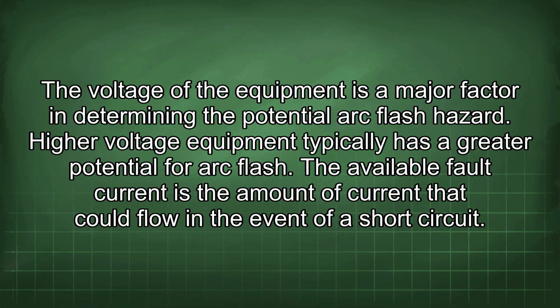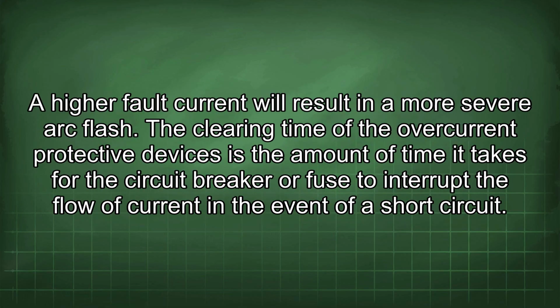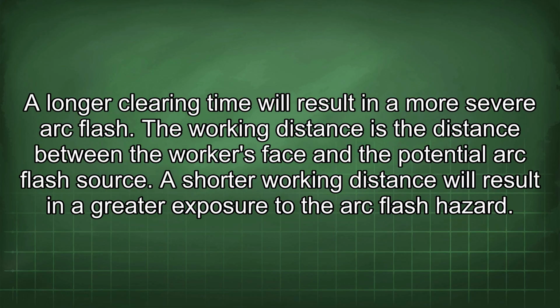Higher voltage equipment typically has a greater potential for arc flash. The available fault current is the amount of current that could flow in the event of a short circuit. A higher fault current will result in a more severe arc flash. The clearing time of the overcurrent protective devices is the amount of time it takes for the circuit breaker or fuse to interrupt the flow of current in the event of a short circuit. A longer clearing time will result in a more severe arc flash.